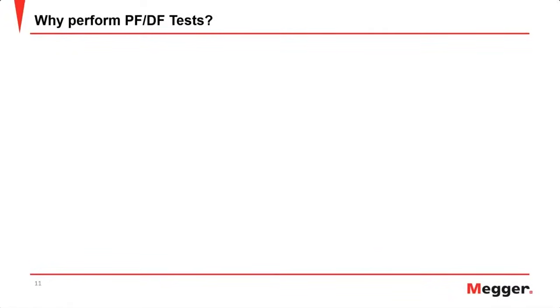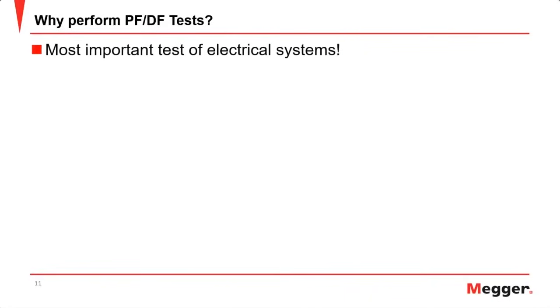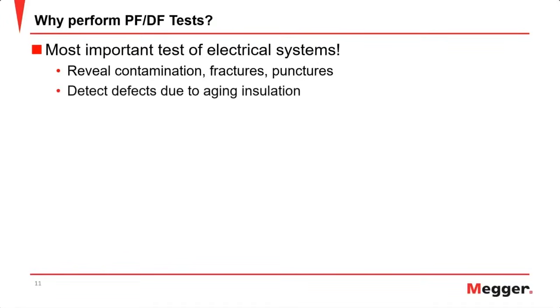So why do we perform power factor or dissipation factor tests? It is the most important test of an electrical system for a couple of reasons. The first is to ensure that the paper and the oil don't have any contamination. There are no fractures or punctures within that paper insulation. And then also to try to identify when the transformer or bushing is starting to show signs of age. When you can detect the insulation changing over time, that allows you to improve your system.